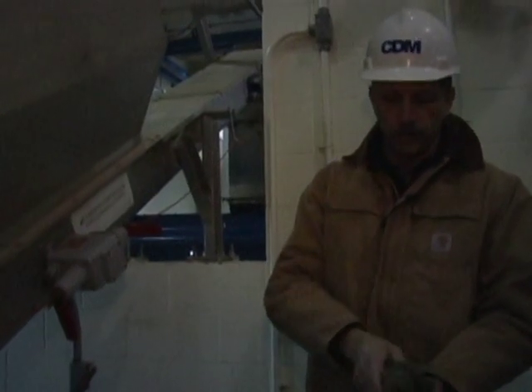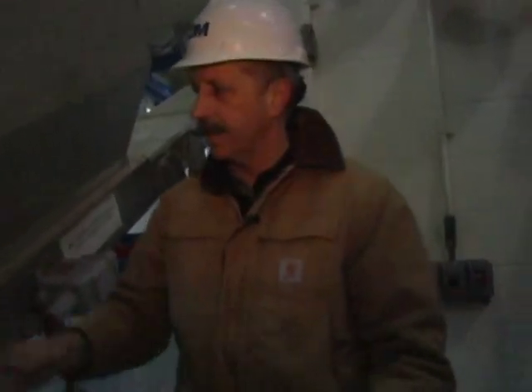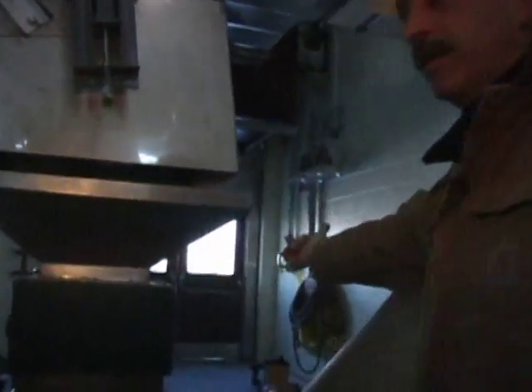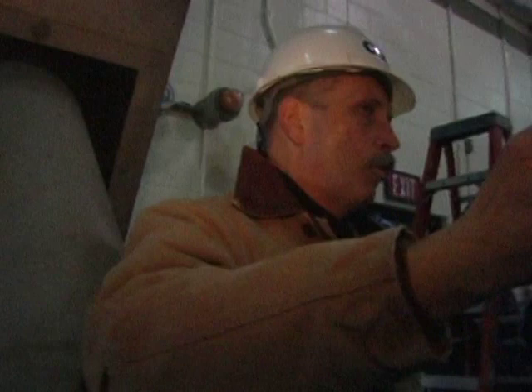The wash press control, here again, there's a local control in the field, which is located on the other side of the unit. Back on the wall is an emergency stop switch, as well as a hand-off-auto switch for both the grinder as well as the auger itself. Locally at the equipment, you can run the auger or the grinder itself individually. Back at the control panel, it runs as a complete unit. For troubleshooting it here locally, you can run either one individually in hand.